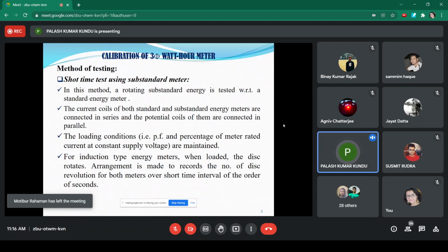What is the name of the testing? Short time test. Short time test means the test in which the error in the meter constant, the percentage error in the meter constant, should be measured. That is called the short time test. So what is the description of the short time test?